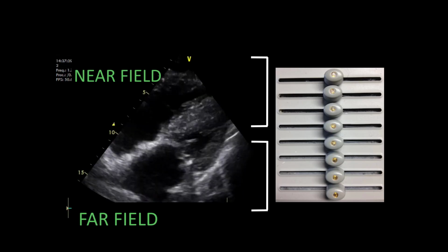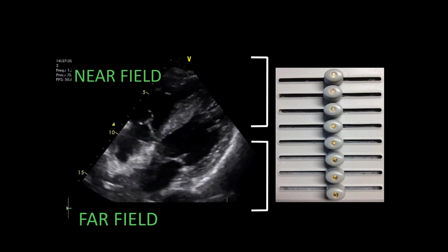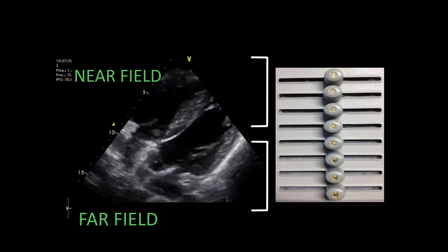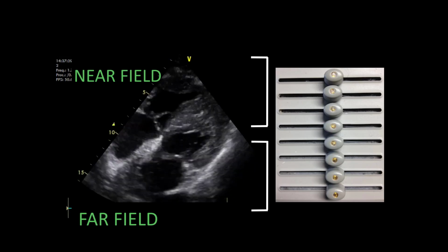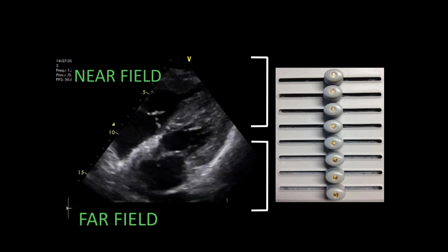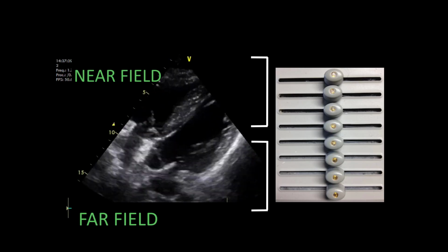This is done using the time gain compensation. Simply, it takes longer for a deeper structure to have an ultrasound reflect on it. We can thus amplify the signal in order to display it with the same intensity as tissues close to the transducer. It is important to understand that we are not generating more signal, we're just amplifying whatever comes back.